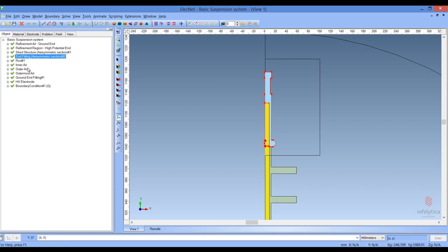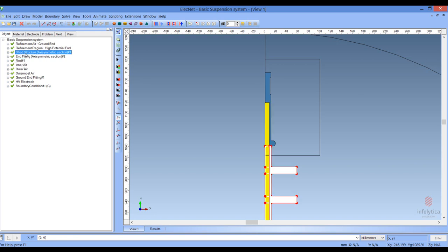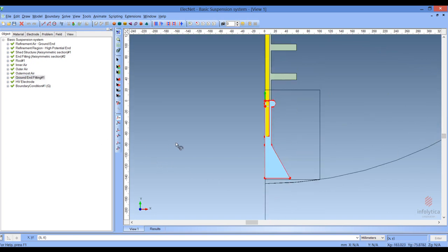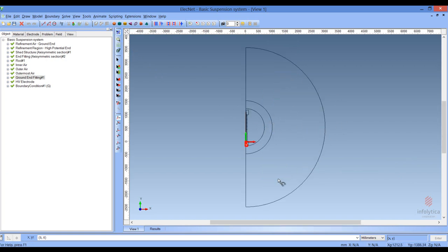We have the various volumes that form the insulation string: the end fittings, the high-potential end fitting, the rod down the center, and the shed structure. Going down to the bottom we will see the ground end of the structure. Some of the other structures added here are for controlling the solution mesh density, which is typical for solving finite element problems. We also have inner and outer air structures, because the field will extend out into those areas and we need elements to model the electric field there.